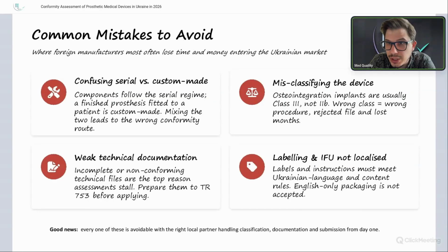Then this is actually what I had experience with. We did not receive any fines, but we had to help the European Union manufacturer from Germany to develop technical documentation. What did we see? We received the package of technical documentation, but inside this package there were no ISO 10328 reports, and for liners it did not contain ISO 10993 biocompatibility results, and we saw that the ISO 14971 risk analysis was not updated according to the latest version of the standard. There was no new version of the standards anywhere in the documentation.